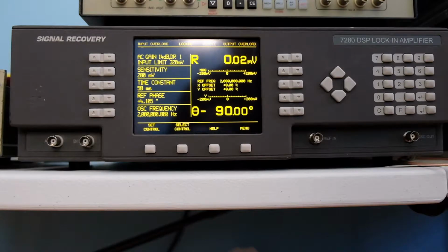So this lock-in amplifier goes from very low frequencies like a few hertz up to 2 megahertz, and I'm going to use the highest frequency because I'm going to get the highest phase difference for a given cable length. I can use lower frequencies, but then the accuracy of the measurement is going to degrade as the phase difference will be small for low frequency.